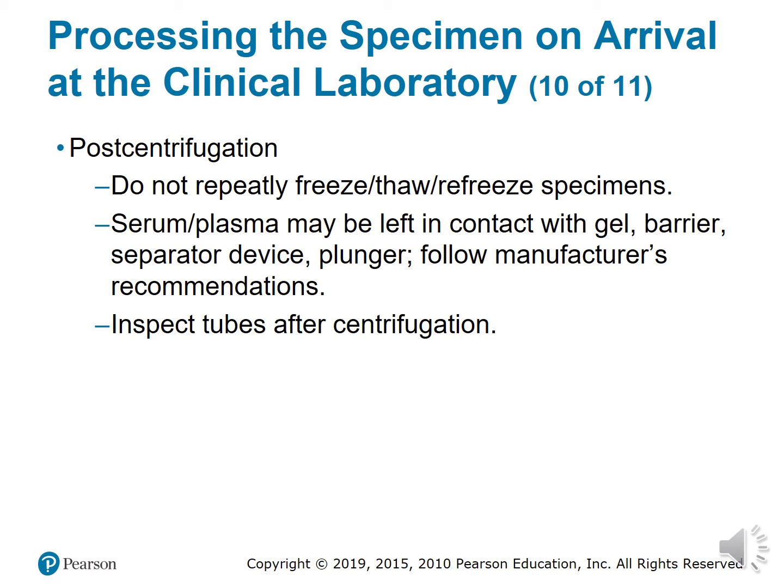You just simply want to make sure that it's not expired, make sure there are no cracks and things of that nature, because if a tube breaks inside the centrifuge, that will throw the centrifuge off and is going to warrant repairs. I just recently shared with you all how much that will cost on average to get it fixed.